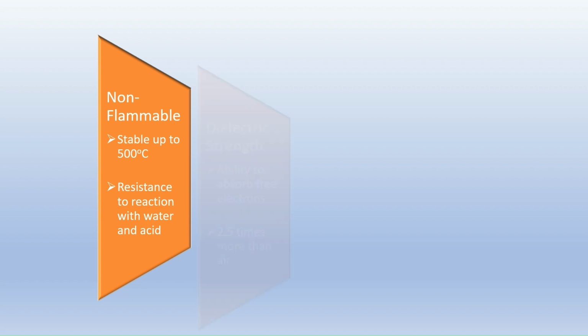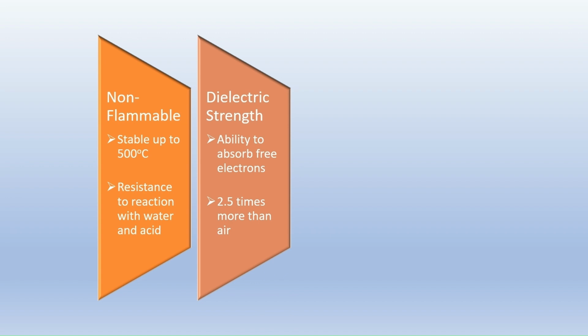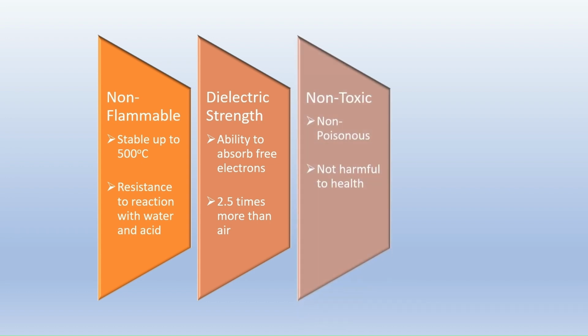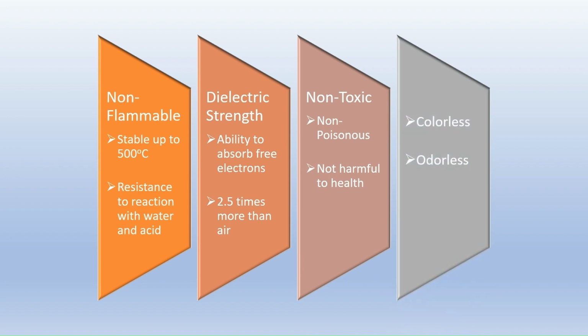The second property is that, due to its ability to absorb free electrons, SF6 gas has excellent dielectric strength, which is about 2.5 times that of air. SF6 gas is non-poisonous and therefore not harmful to health. Other properties of SF6 gas are that it is colorless or transparent, and it doesn't have any smell. Due to all these benefits, SF6 circuit breakers are preferred in a wide voltage range from 36 kV to 765 kV.